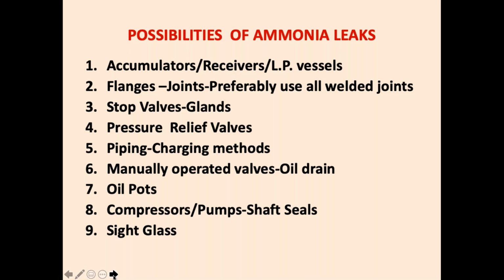The possibility of leak also exists from sight glasses. If the sight glass breaks, or if they do not have the non-return valves at the inlet and outlet, when the sight glass breaks, if it doesn't close the main receiver outlet lines, there would be heavy leakages. So these are the areas where ammonia leaks.